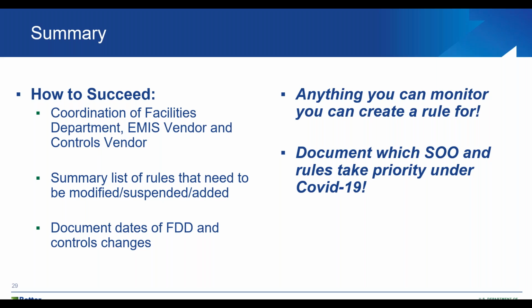And I like to mention, I've looked at hundreds of thousands of data points, and two of the main things I like to indicate is anything you can monitor, you can create a rule for. So the more data that you can bring in, the more successful you can be. It doesn't mean you need all the data points, but it's good to have it available. And document the sequence of operation and the rules. So which ones take priority? Documentation and availability of points to monitor provide for a much easier time to be successful.